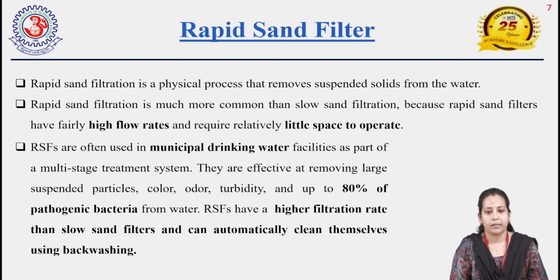Going forward, that is the rapid sand filter. What is rapid sand filtration? It is a physical process that removes suspended solids which may not be removed in the stage of sedimentation and sedimentation with coagulation. So to remove other floating materials or suspended particles in water, most water treatment plants adopt rapid sand filtration, and these are more common than the slow sand filter, because the rapid sand filter has a fairly high flow rate, requires very little space to operate, and is easy to operate also.